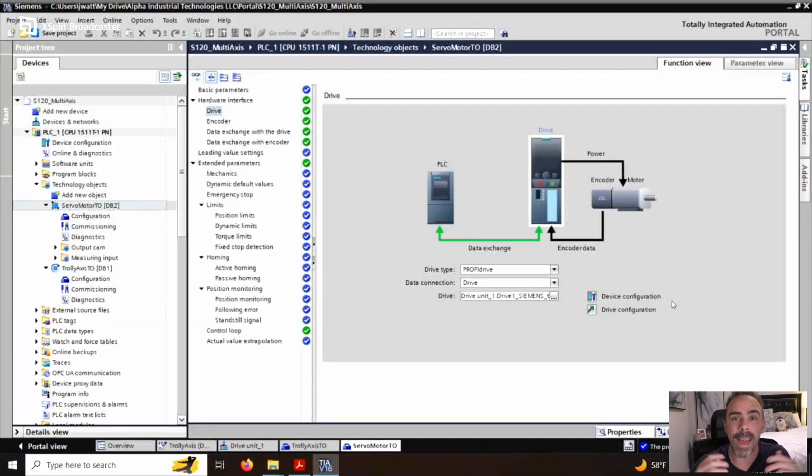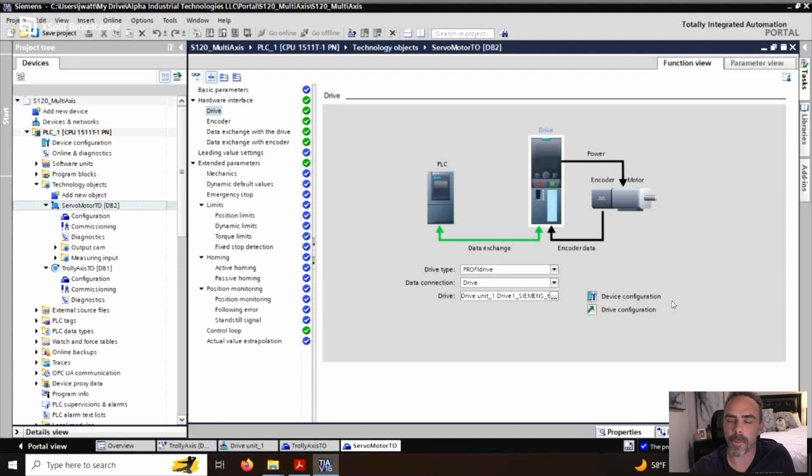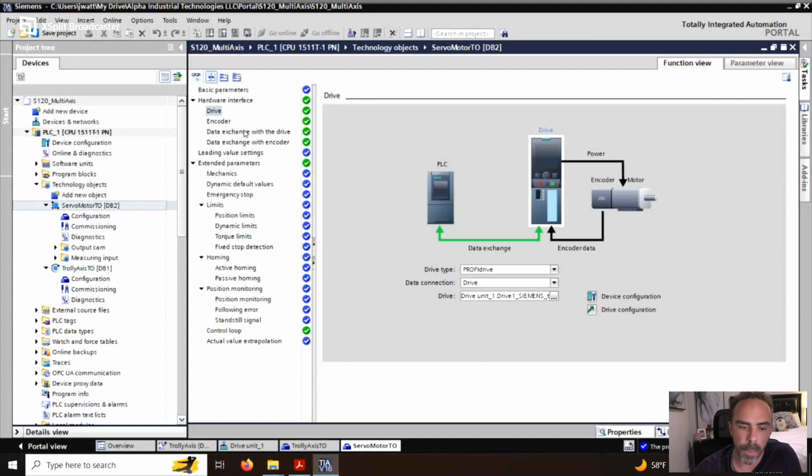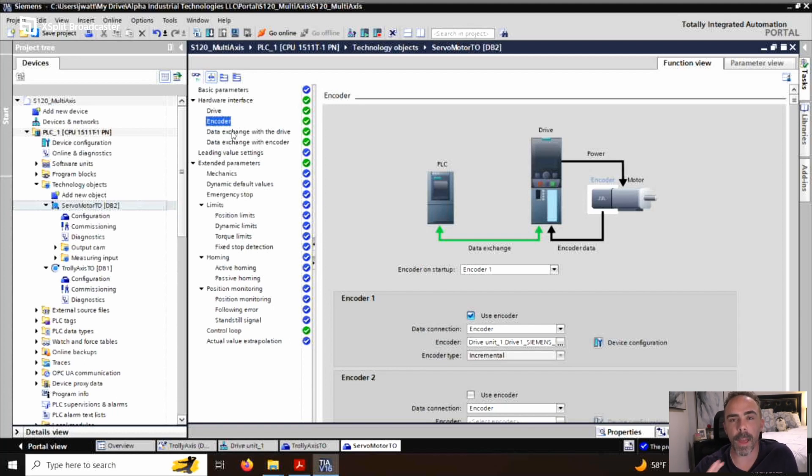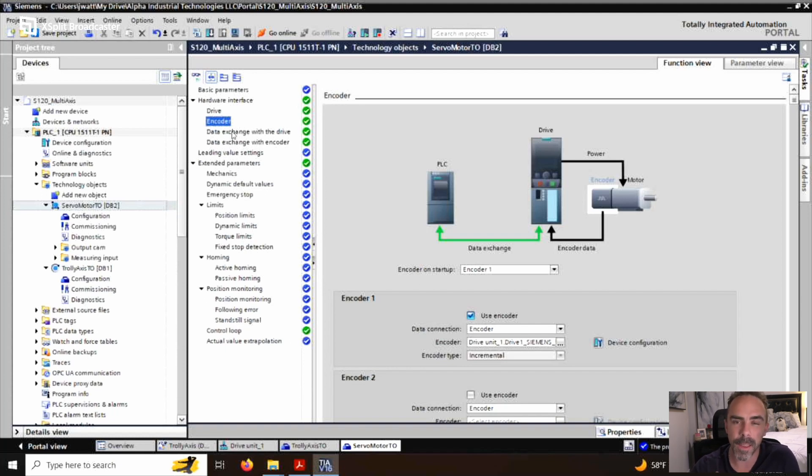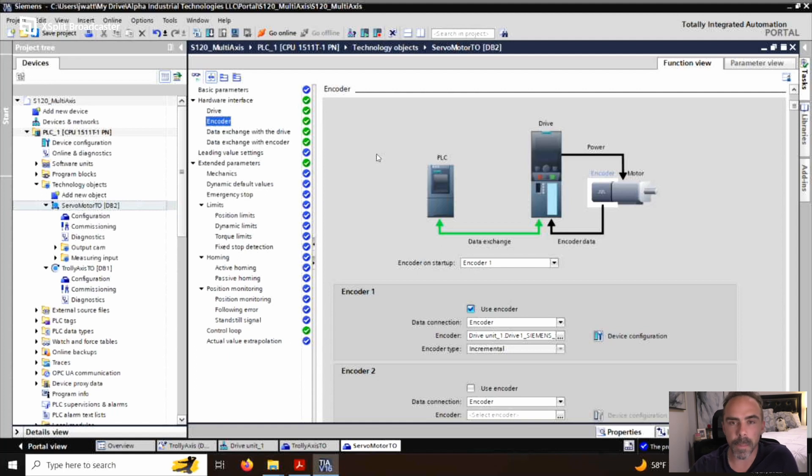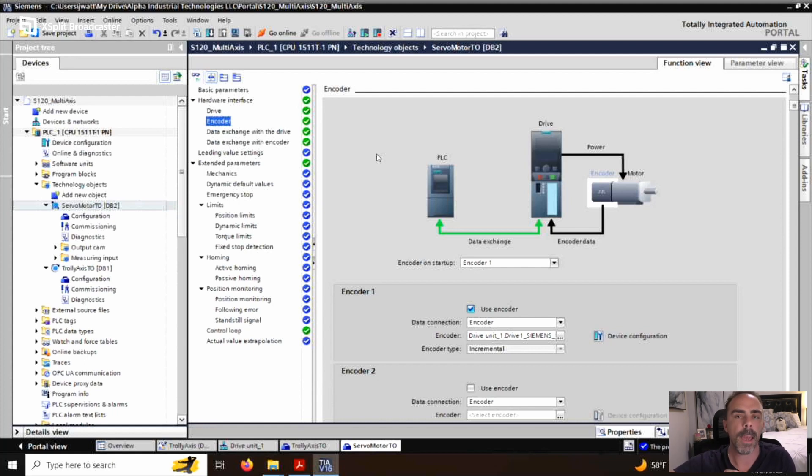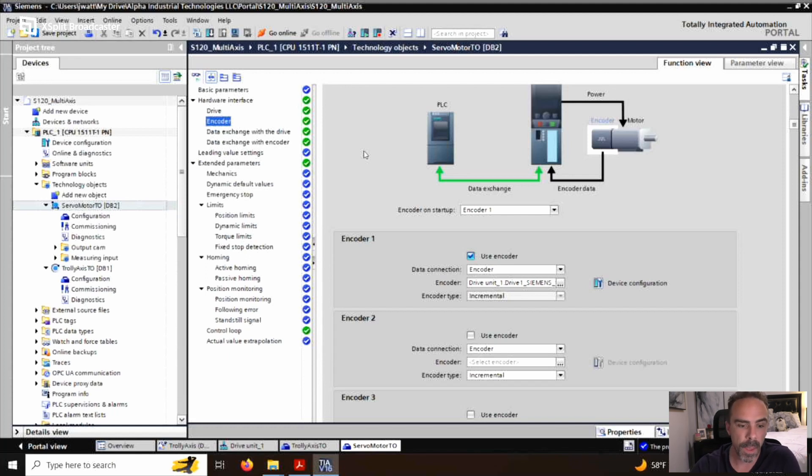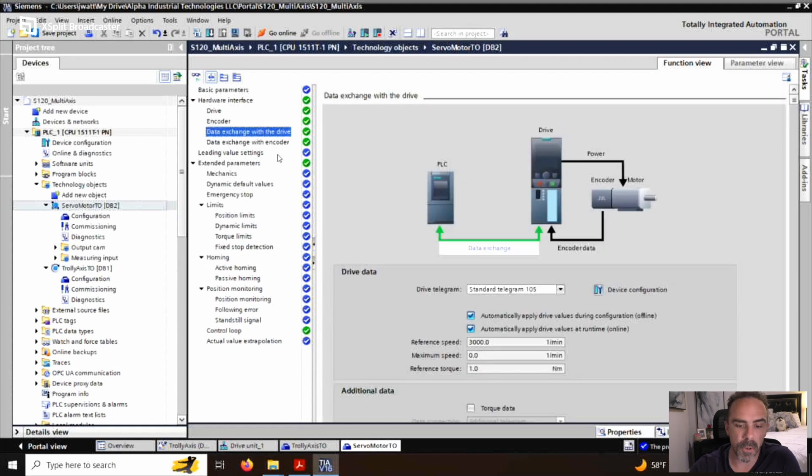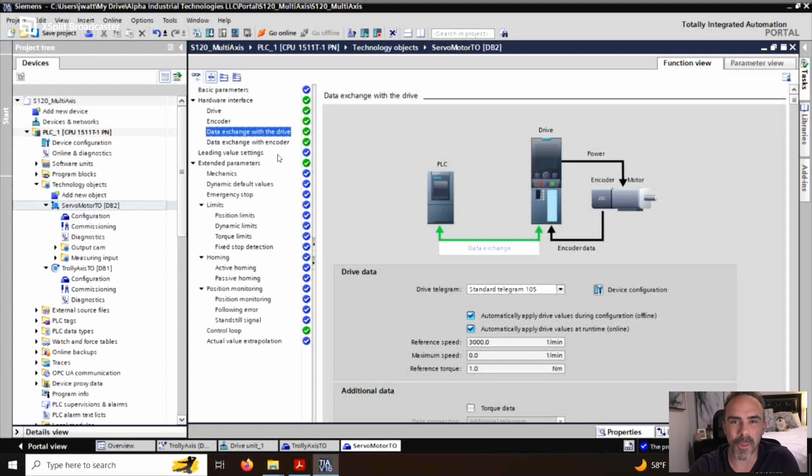Now, once again, magically, all of the check boxes go green because, well, frankly, I wanted it to happen that way. And so that's why we set everything up. Let's go through and look at them. If they weren't green, you might have to set up an encoder because remember Siemens gives you the flexibility to do absolutely anything you want to do. But if you kind of do things in the right order and then just kind of the standard way, you tend to not run into that trouble. So the data exchange with a drive, just like on the other axis, we set it up as 105 before. And then what is up with this data exchange with encoder? The encoder doesn't necessarily have to be on the axis itself.